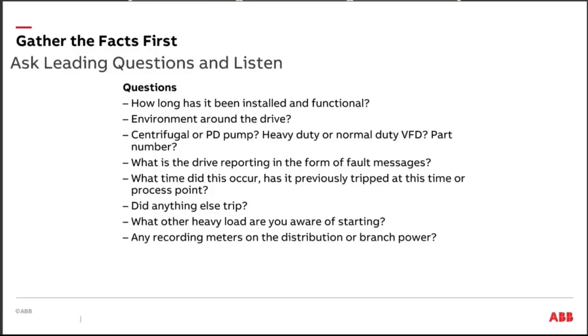So one of the very first things you want to know is, how long has this drive been installed? Is this a brand new startup, or has this thing been out there running for 3 years or 5 years or something? Because the length of time is going to take you down all kinds of different paths of troubleshooting. So you want to know how long it's been installed and running, and has it always been functional? Is everything going? What's going on with it?